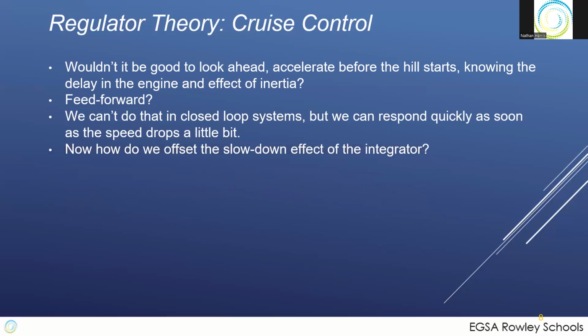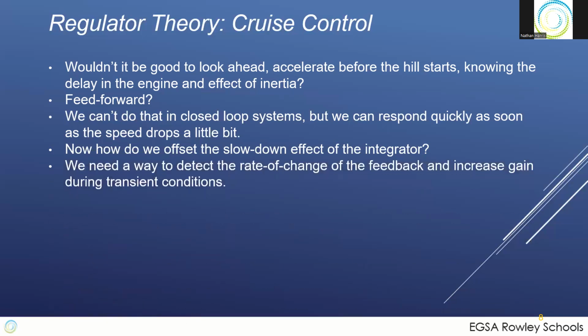So now we offset the slowdown. We added the proportional. We increased the integral to slow it down. But during a quick transient condition, we want to add some gain. We want to add some gain during the rate of change of a signal. So if we drop off quickly, we want to hit it quickly. So if we add an impact load, let's say we drop a large load onto a generator, a large motor load, for example, we want to kick that AVR, we want to kick that governor in hard and fast. And that's the differentiator.